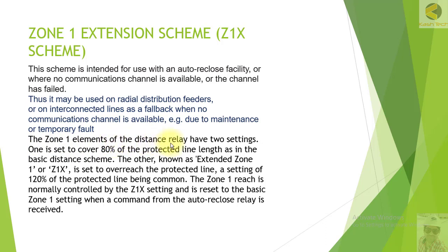The Zone 1 elements of the distance relay have two settings. One is set to cover 80% of the protected line length as in the basic distance scheme. The other, known as Extended Zone 1 or Z1X, is set to overreach the protected line — a setting of 120% of the protected line being common. The Zone 1 reach is normally controlled by Z1X settings and is reset to basic Zone 1 settings when a command from the auto-reclose relay is received.